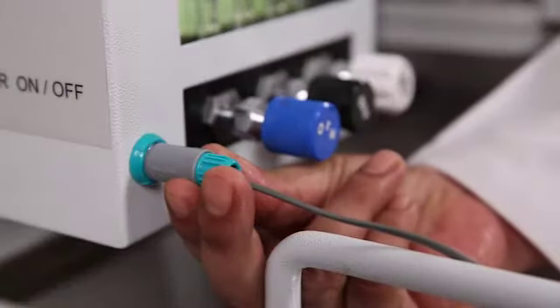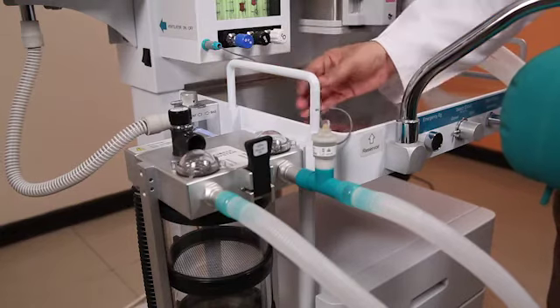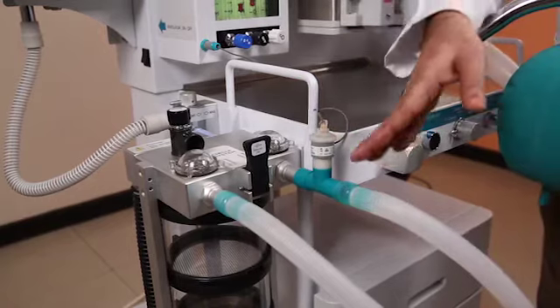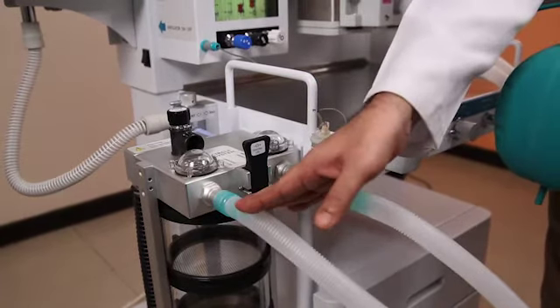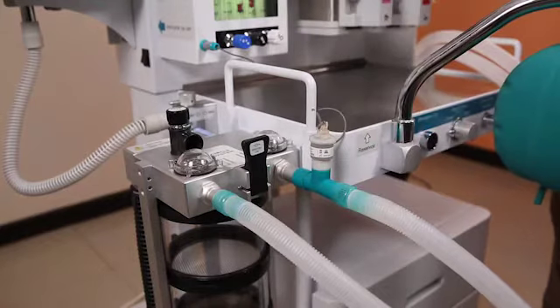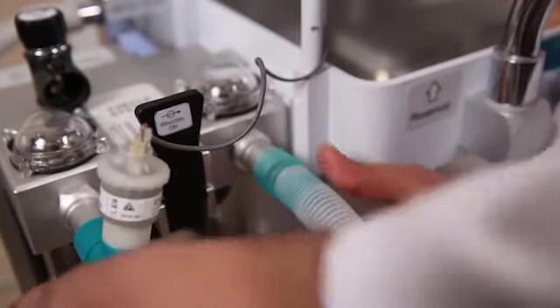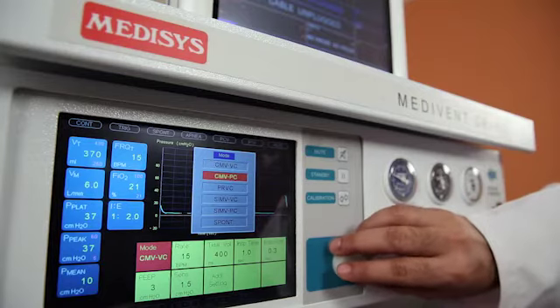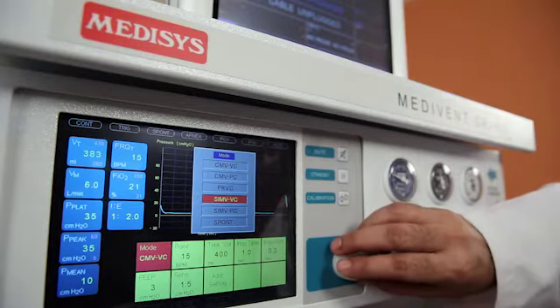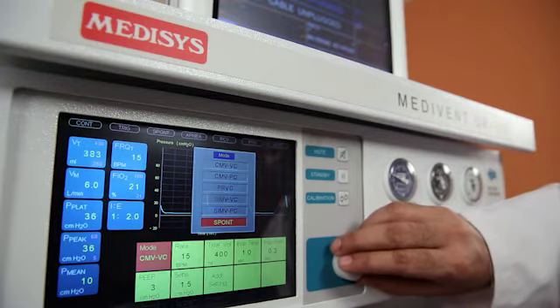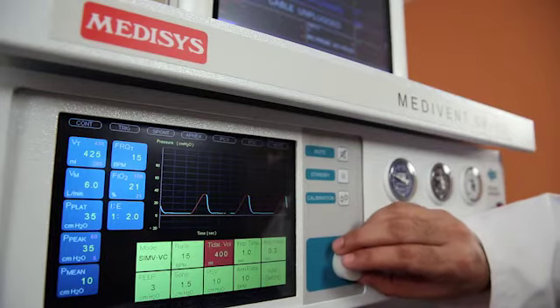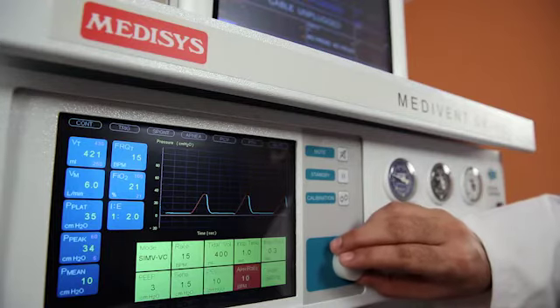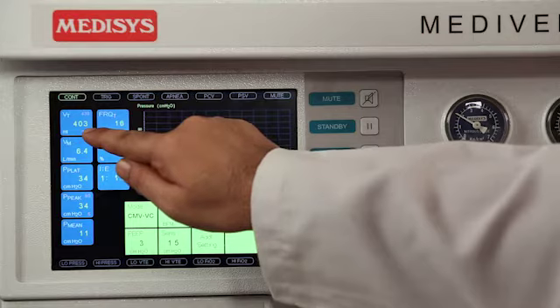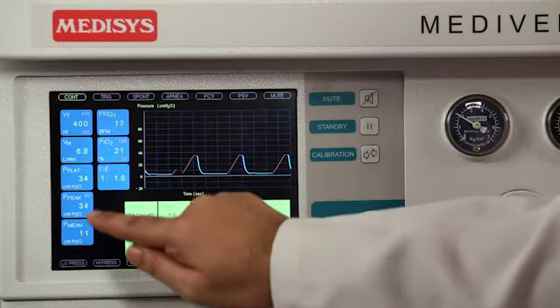To check the oxygen flow, we have a very sensitive oxygen analyzer incorporated in the machine. It is externally visible, and the sensors can be put in the inspiratory limb of the circuit or in the expiratory limb of the circuit. By that I mean they are interchangeable. The machine offers you a very easy way of selecting the mode of ventilation. With a flick of one switch, you can change from one mode to another, which is very easily visible, and it is also depicted in the data displayed on the screen, which will also show the changes it produces in the machine parameters.